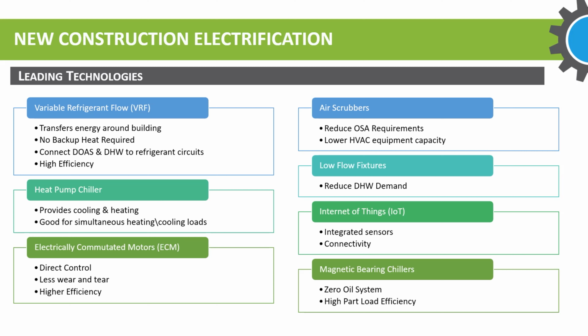Air scrubbers reduce outside air, which can reduce your HVAC equipment load and capacity. I've done numerous calculations and recommendations to owners on utilizing air scrubbers to pull out or extract CO2 from the air in the building and then release it at off hours. That's changed and reduced the size of equipment and their energy performance.